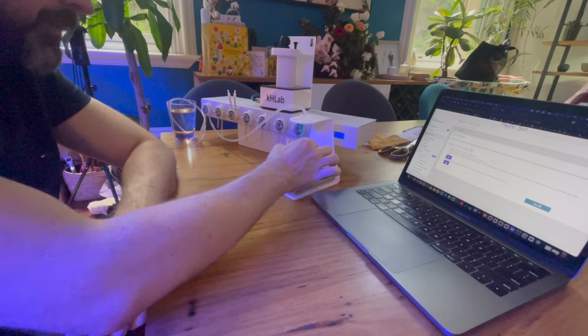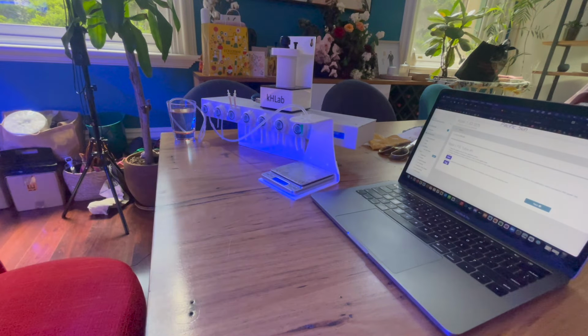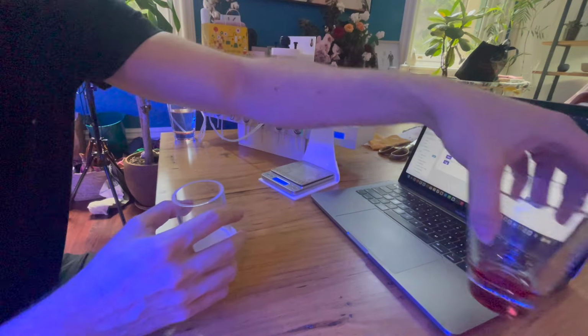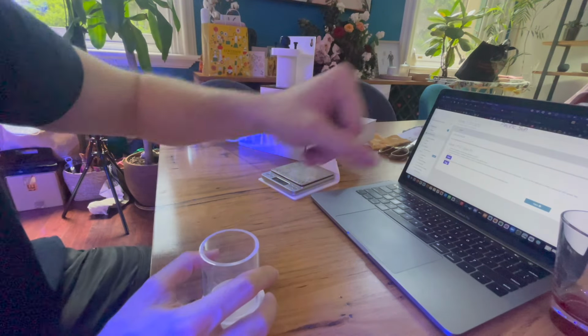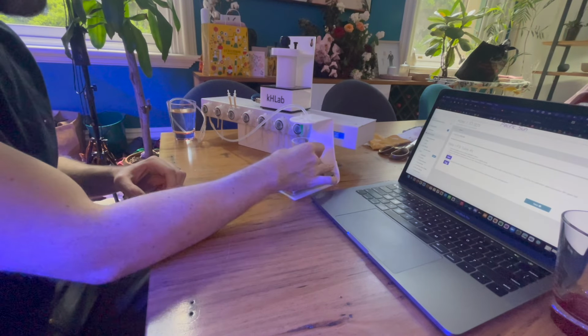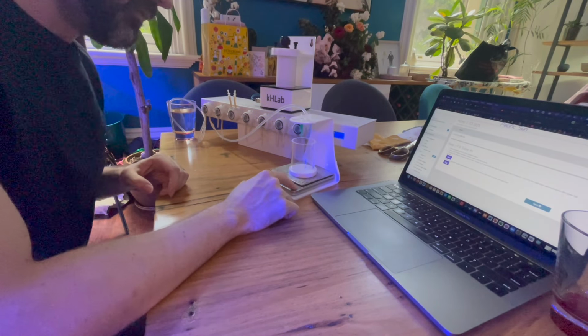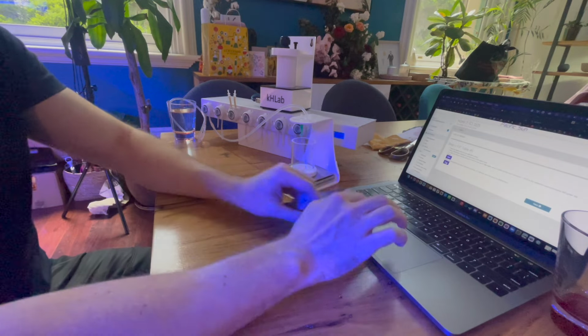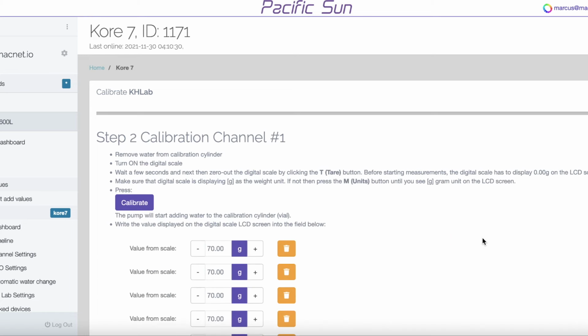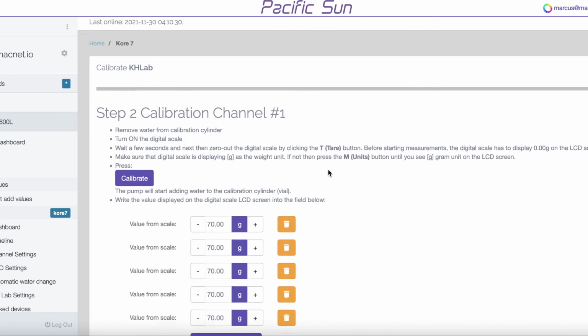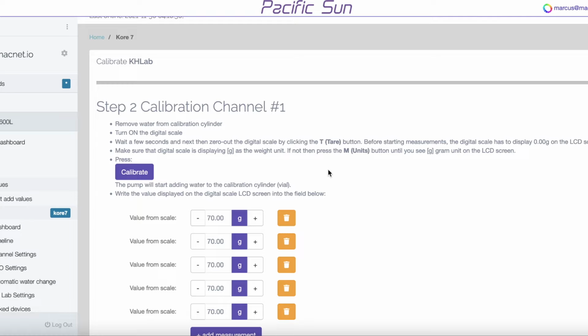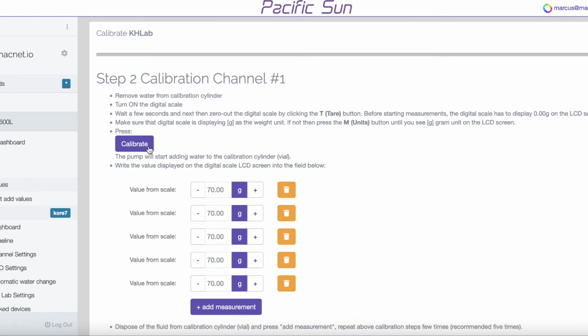Now we can empty the vial. Just have an empty glass here off shot, what I'm going to use is just emptying the vial. So the vial's empty again. Put it back. Make sure it's reset to 0. Press next on the screen, and this is the calibration screen. So we have a fully primed line. We have the scale set to 0. This vial here empty, and all you need to do is press the calibrate button.